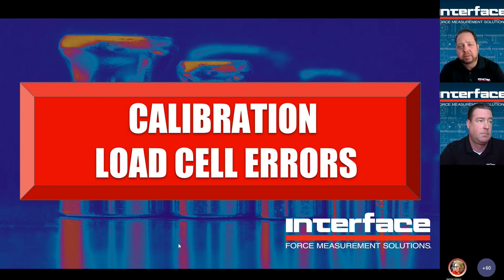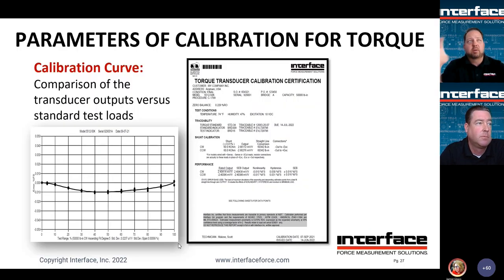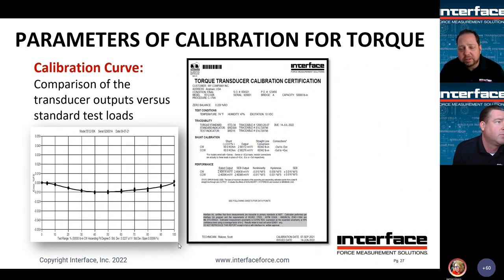So, load cell errors. This is a little more straightforward. We talked about overall uncertainty. Now we'll start talking a little bit about what kind of errors you get from a calibration. So here's a sample CalCert for a 5500 series reference torque sensor. You've got the traceability information at the top. First, you've got, of course, DUT information. You've got traceability information. There are the lab test conditions, which should be relatively static, of course, in most calibration labs. Provided shunt cal. And then we've got the performance. We've got both directions. We've got the nonlinearity, hysteresis, and then we provide SEB values. And I'll talk a little bit more about what that means.